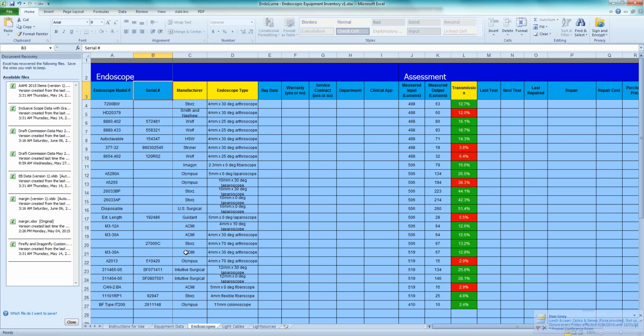Even with that, as you're probably seeing in your own home with light bulbs, they come with a rating on the package for how long they should last, but it doesn't mean they're always going to last that long. So even then, if you get a complaint of a dim light source and the hours are only, say, 450 when it's supposed to be replaced at 500, it could still be that the bulb is the problem. So it would actually be misleading to just use the hour meter at that point. The Endo Illume would let you make certain whether the bulb, the cable, or the scope is the problem.